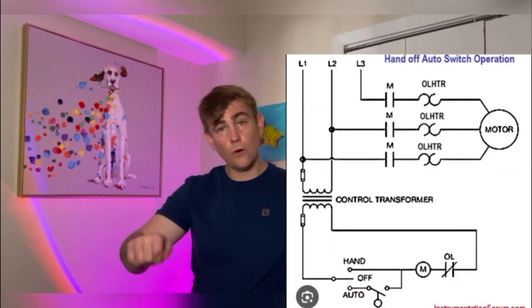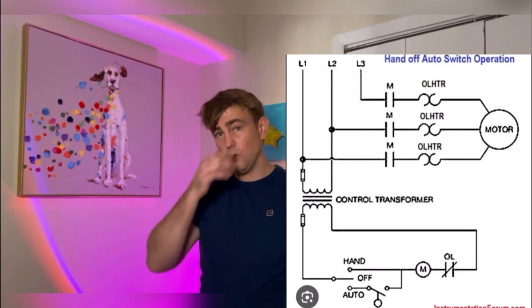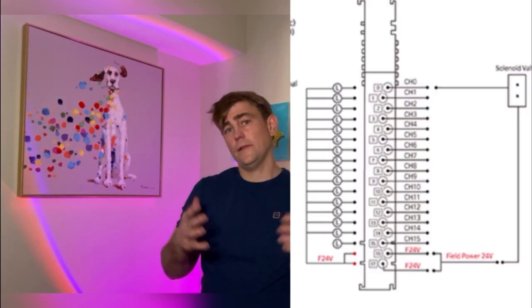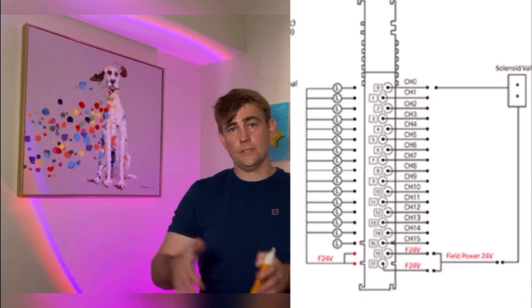In this system, we're pretty much just using float switches. We could generate that signal to turn on. You could have a selector switch, and maybe you put it into manual mode or automatic mode. Maybe you have a PLC discrete output. That's the first step. That discrete output energizes your circuit. Yeah, so that's just a little bit of that stuff.